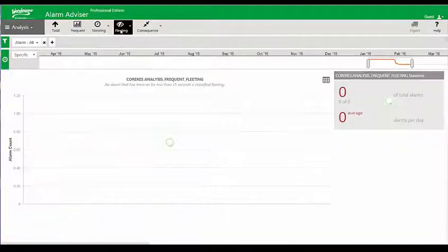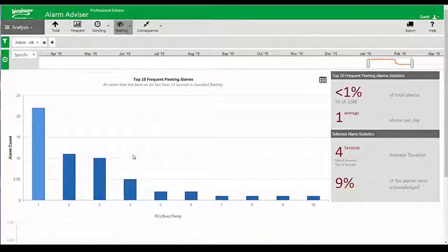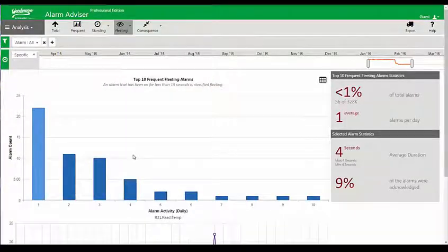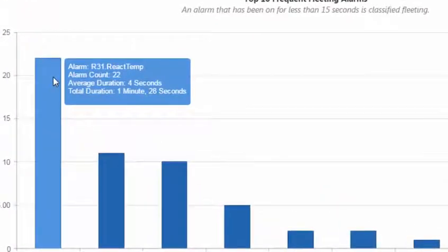Another graph in this toolbox is the ability to see fleeting alarms — alarms that come on very frequently but with very short duration. I hover over the actual alarm and it tells me how long that alarm has been coming in. These alarms need some attention; you need to go out there and put some debounce timers on those alarms.